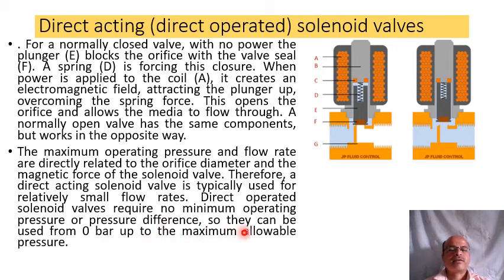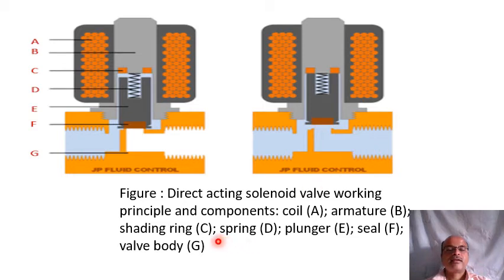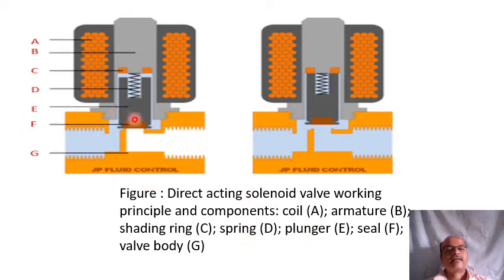Direct operated solenoid valves require no minimum operating pressure or pressure difference, so they can be used from zero bar up to maximum allowable pressure. In the diagram: A is the coil, B is the armature, C is the shading ring, D is the spring, and E is the plunger. Due to generation of the magnetic field, the plunger moves upward or downward as required to keep the valve open or closed.